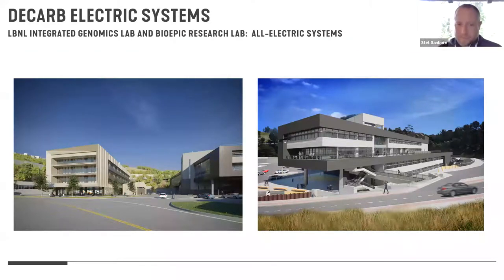On that project, we have far more requirements because of the type of research they're doing. So we have moderate temperature chilled water, low temperature chilled water, industrial hot water, domestic hot water. We have a special research water loop. And so I think we have 6 different temperatures moving through the building. In this case, it's all being controlled by a series of staged water source heat pumps that are doing simultaneous heating and cooling, and then rejecting energy to the combined chilled water system that's split between these two buildings as part of a district loop. So we're able to offset some of the cooling and heating load of the adjacent building because of the district.